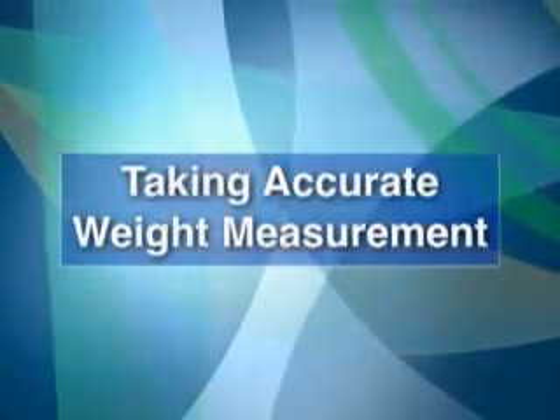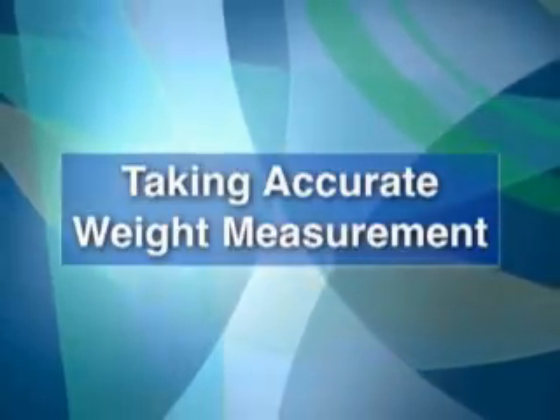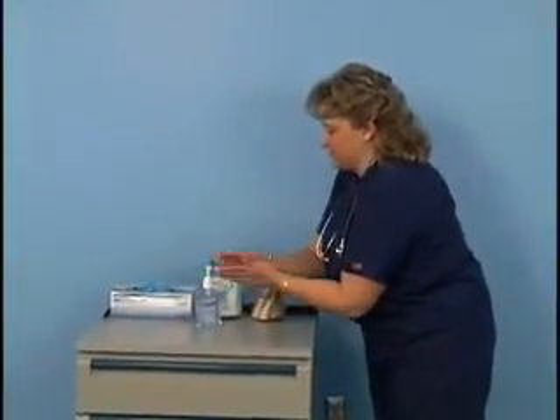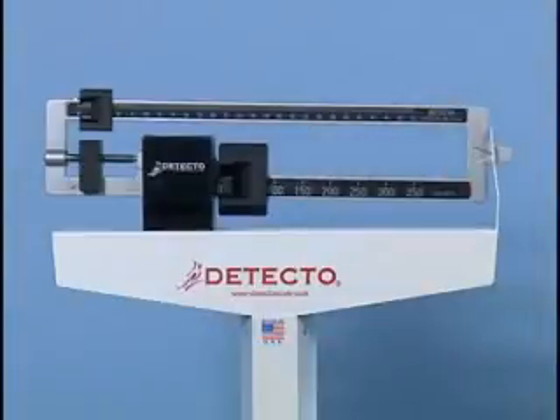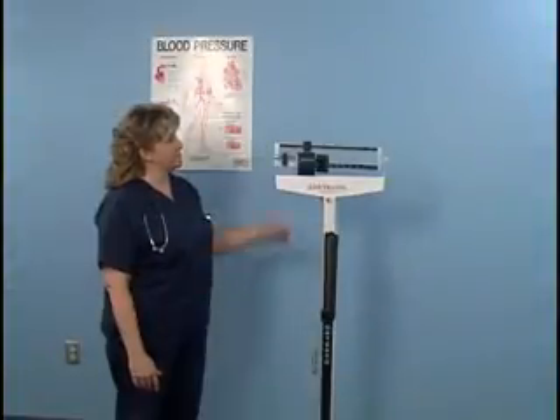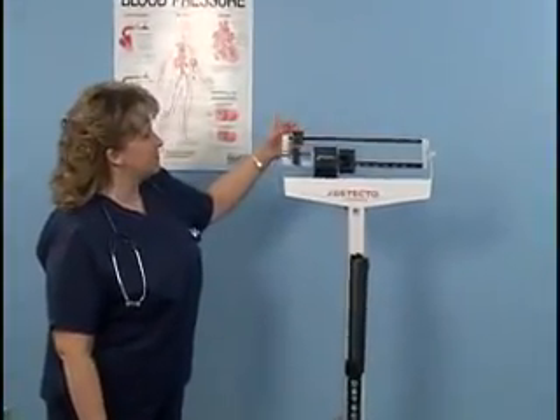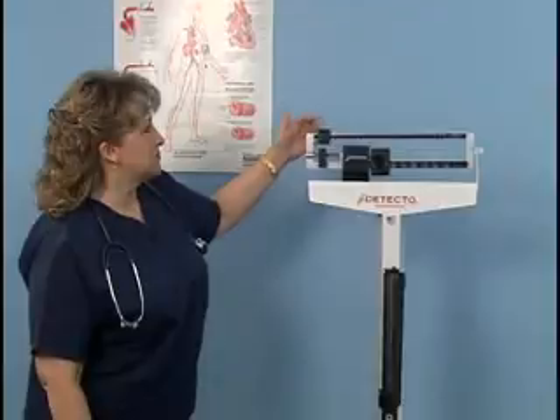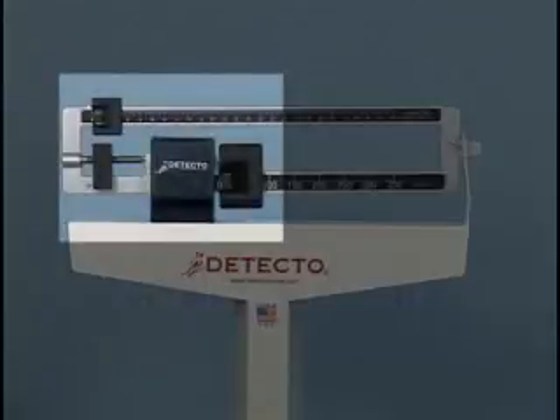First, we will focus on taking an accurate weight measurement. Sanitize your hands before proceeding. Check the balance scale for accuracy. If the scale is not balanced, the weight measurement will be inaccurate. Make sure the upper and lower weights are on 0. They should be positioned all the way to the left of the calibration bars.